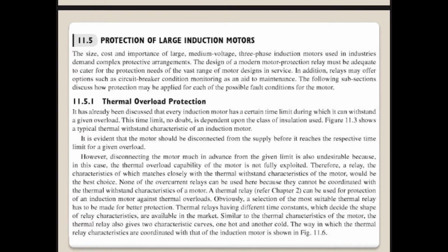Why? Because it's economically not feasible. Economically you cannot justify it because it will become too costly. The motor might not be very expensive, but its protection might be too expensive. Because of that, we don't go for different fault protections. Short circuit and overload protection is more than enough. For that, fuses and thermal relays are sufficient.